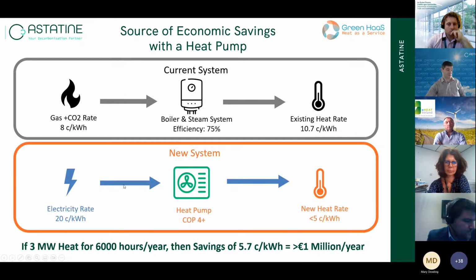And if you do a comparison on the heat pump side, you can look at your electricity rate and then look at the heat pump efficiency. A typical efficiency on a dairy site is usually more than 4. So if you take a typical example of a COP of 4, divide your electricity rate by that COP of 4, and you get the new heat rate that you'd have with a heat pump. You can see in this particular example, based on this client's rates, they had a heat rate that was about half with the heat pump compared to what it was with fossil fuels.